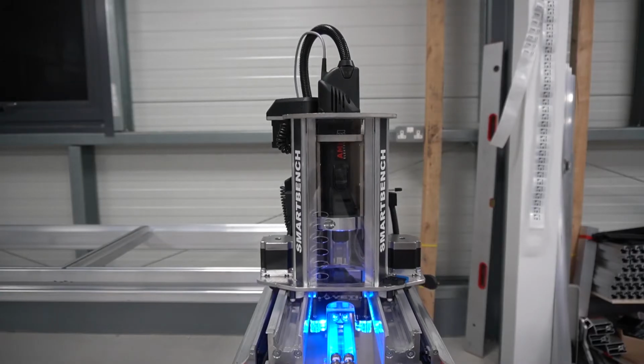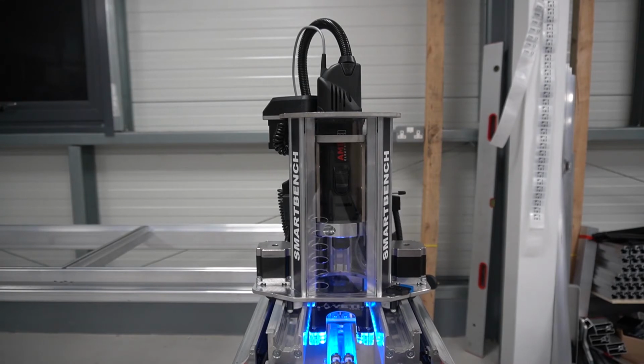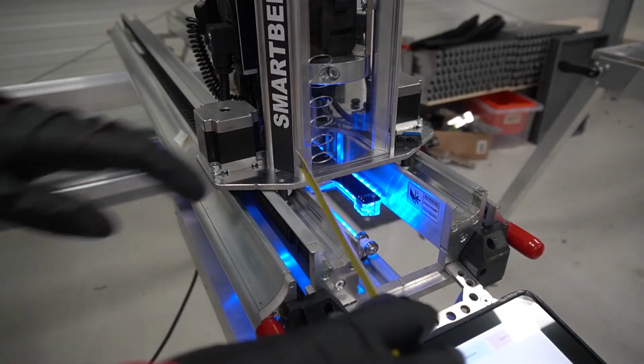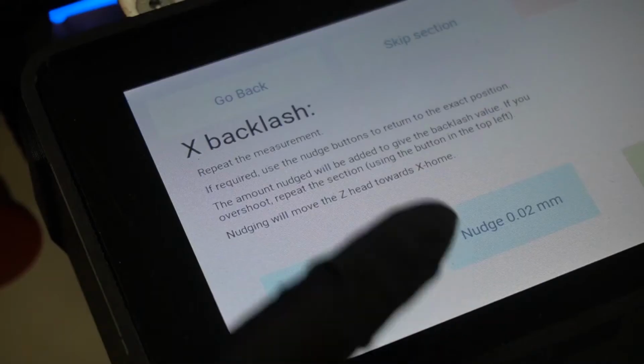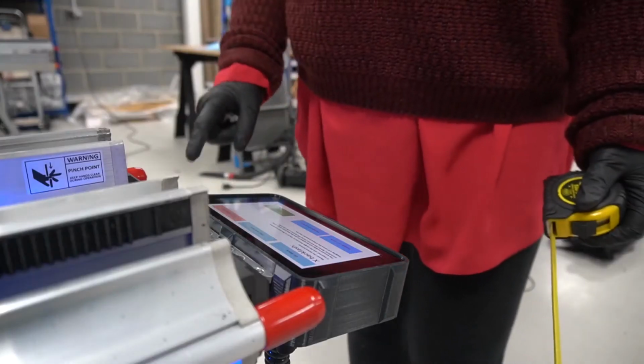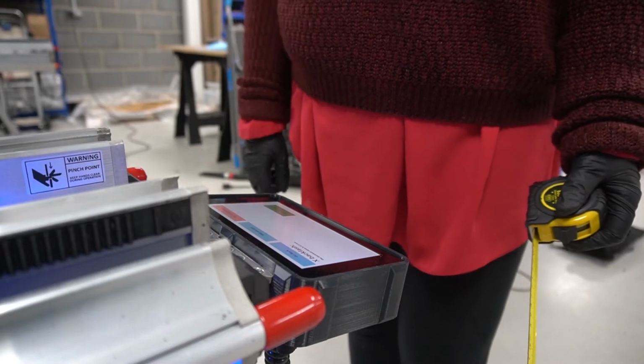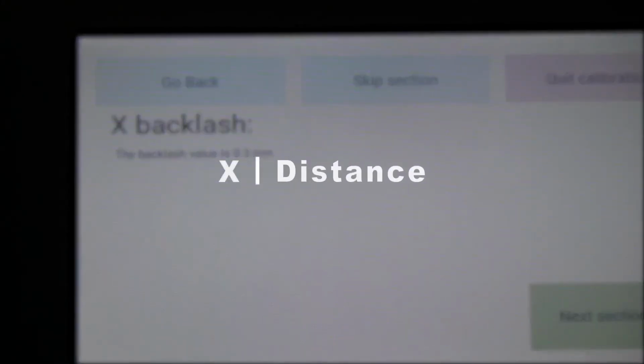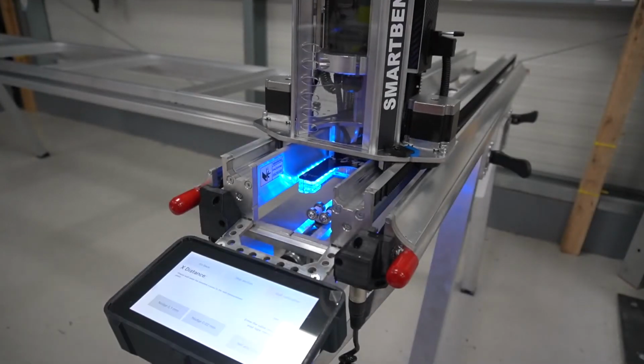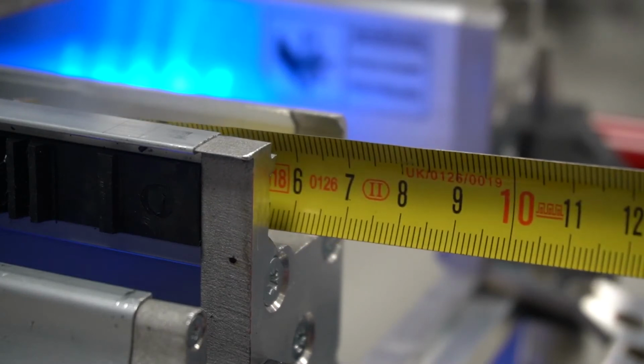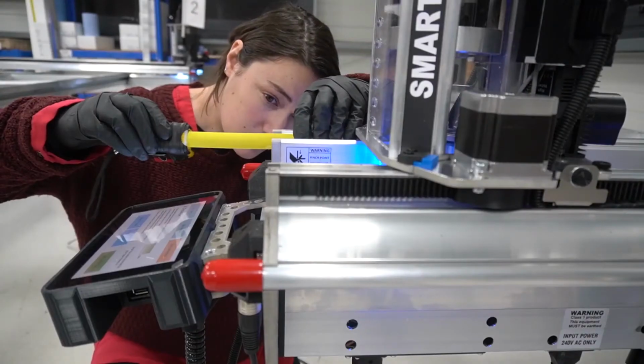The axis will be moved backwards and forwards, attempting to return to the same point. Repeat your measurement again, and if necessary, use the nudge buttons to return to the same position. When you're happy the measurement is the same, press OK and you will be told the backlash value. To measure the X distance, place the tape as before and use the nudge buttons so that the measurement is precisely up to a millimetre line.